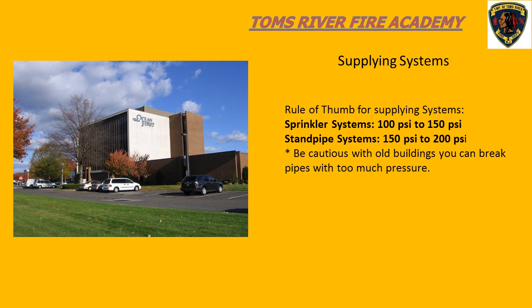Some rules of thumb for pumping to sprinkler and standpipes: pretty simple. If we're dealing with a sprinkler system, we just want to pump 100 to 150 psi into the fire department connection. If we're dealing with a standpipe system, or if we're dealing with a combination system and we know we're going to be using a standpipe, we want to pump 150 to 200 psi into the fire department connection.